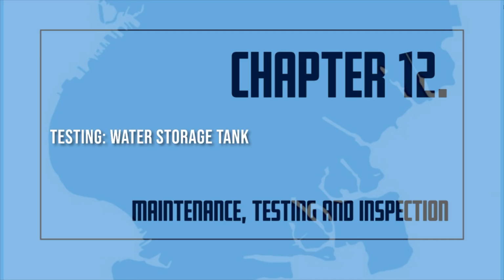C. Water storage tank. Temperature alarms. Low water temperature alarms shall be tested monthly, in cold weather only. High temperature limit switches. High water temperature limit switches on tank heating systems shall be tested monthly, whenever the heating system is in service. Water level alarms. High and low water level alarms shall be tested semi-annually. Level indicator. Level indicators shall be tested every 5 years for accuracy and freedom of movement. Pressure gauges. Pressure gauges shall be tested every 5 years with a calibrated gauge according to the manufacturer's manual. Gauges not accurate to within 3% of the scale of the gauge being tested shall be recalibrated or replaced.